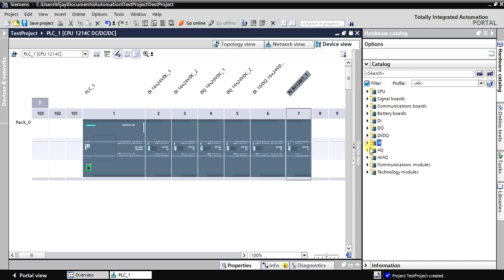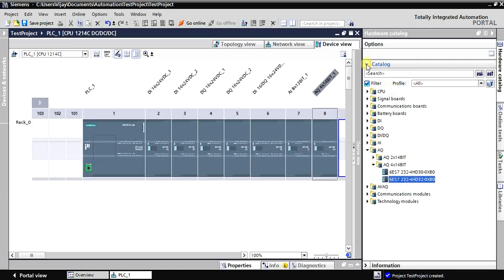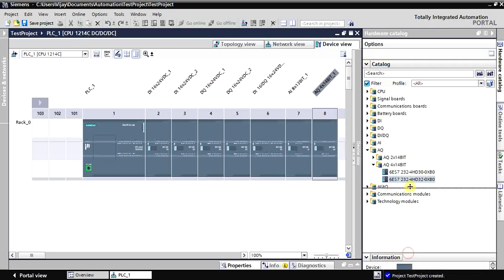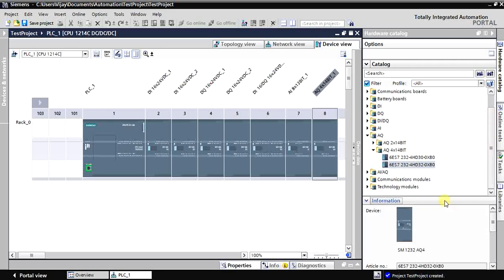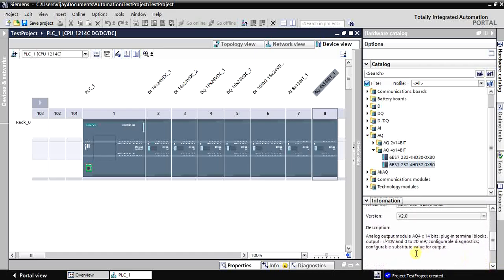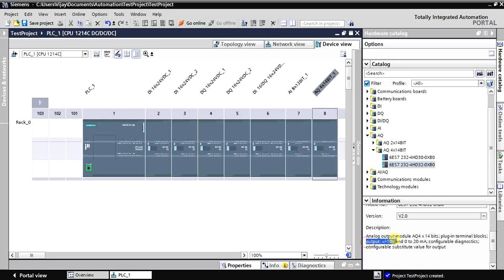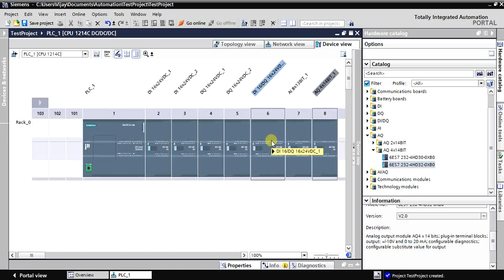Now let's select the analog output module. You can check the article numbers and the output details here. I'm choosing a 4-channel analog output that supports both 0–10V and 0–20mA, so you can use both current and voltage for all four analog outputs. We've now configured DI, DO, analog input, and analog output modules.